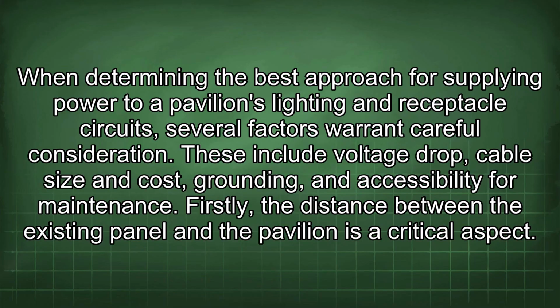When determining the best approach for supplying power to a pavilion's lighting and receptacle circuits, several factors warrant careful consideration. These include voltage drop, cable size and cost, grounding, and accessibility for maintenance. Firstly, the distance between the existing panel and the pavilion is a critical aspect.